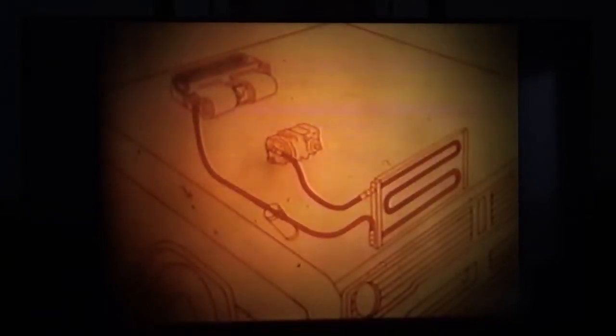From the condenser, the refrigerant enters the receiver dryer unit as a high-pressure, lower-temperature liquid. In the receiver dryer, the refrigerant is stored and moisture is removed by a chemical agent. Next, the liquid refrigerant moves to the expansion valve, which meters the flow of refrigerant into the evaporator. The metering process is controlled by a temperature-sensing bulb attached to a diaphragm on the expansion valve by a capillary tube. The sealed bulb is fastened to the refrigerant return line on the evaporator and is filled with a gas which expands and contracts according to the temperature of the refrigerant leaving the evaporator.